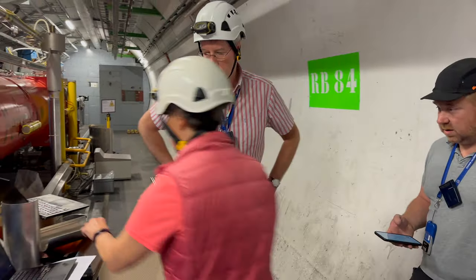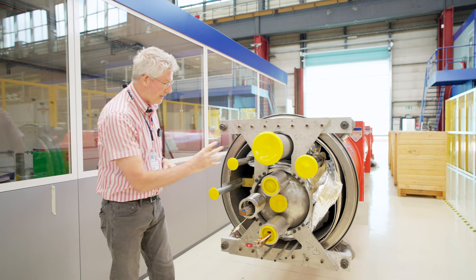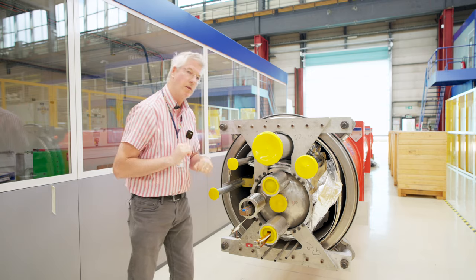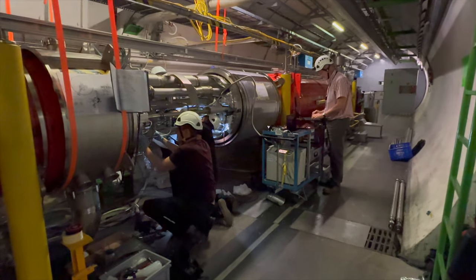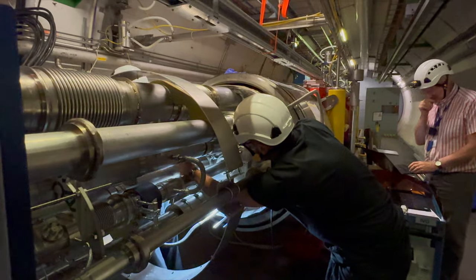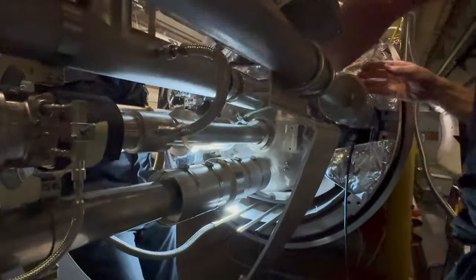When the cryostat was icing, we didn't actually know where the problem was. We did diagnostics to first define which circuit was affected, and were able to confirm very quickly it was on the cold mass circuit. The next step was to decide where longitudinally it was inside this 50-meter object. We could even tell by listening — our leak was so big we could hear it whistling when there was a small overpressure inside the magnet.